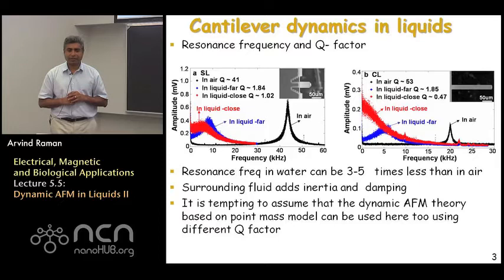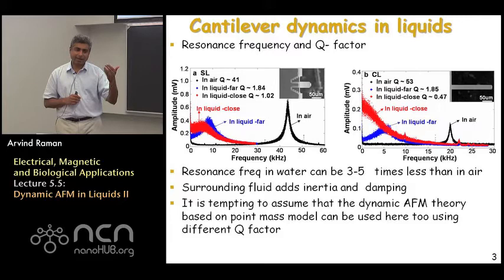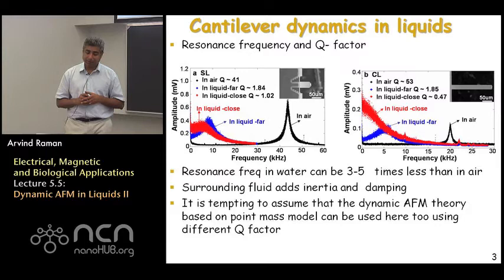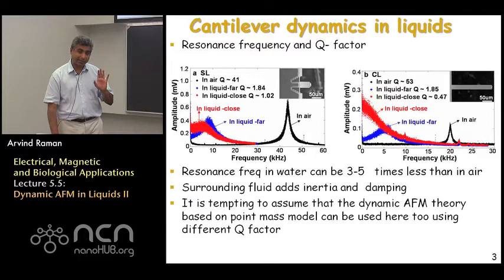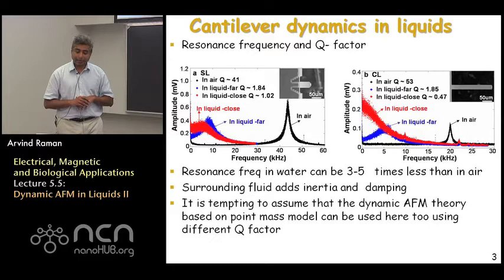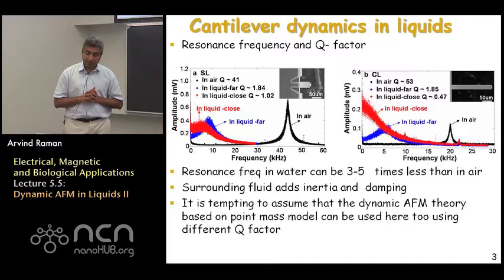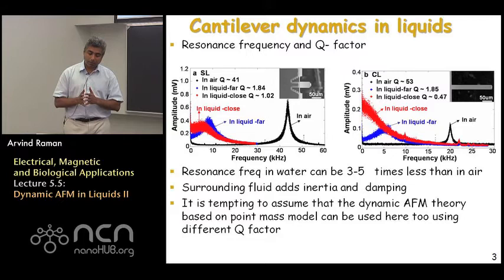The first concept is that the thermally excited resonance of a cantilever in air versus in water is different. On the left is an example of a short biolever — a small cantilever — where the y-axis is the power spectral density and the x-axis is frequency. In air, there is a very sharp resonance peak with a Q factor of about 41 and a resonance frequency between 40 and 50 kHz. When the same cantilever is put in water, shown as the blue curve, the resonance frequency drops from about 45 kHz to just below 10 kHz.